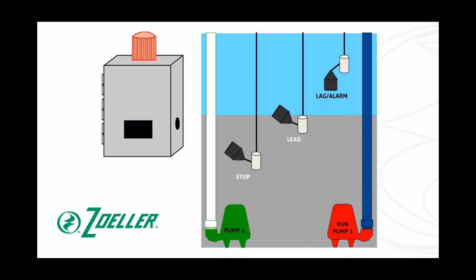And as it's activated, we can see that because this is an alternating duplex control panel, this time it has alternated and is now called for pump 2 to come on. Pump 2 is referred to as our lead pump in this particular scenario. And that's why we refer to that start float as our lead float. It is going to call for the next pump in the sequence to come on. So if it's a duplex operation, it's going to call for pump 1 and then pump 2, pump 1 and then pump 2. And it's going to do that again and again, over and over.